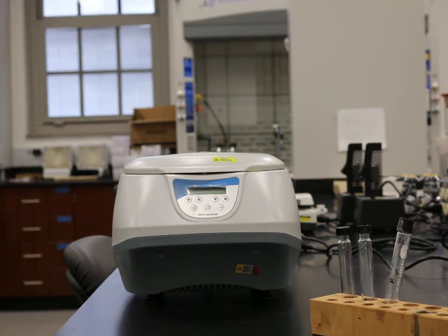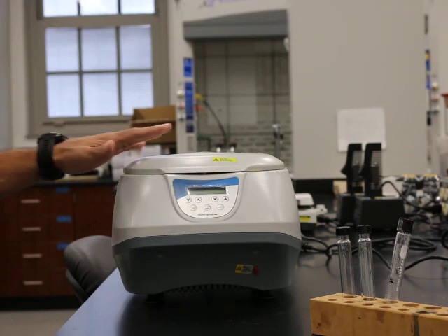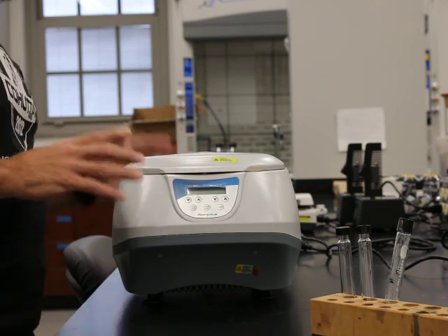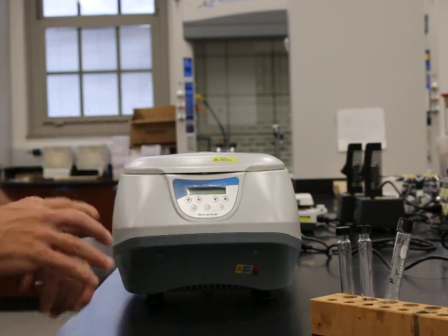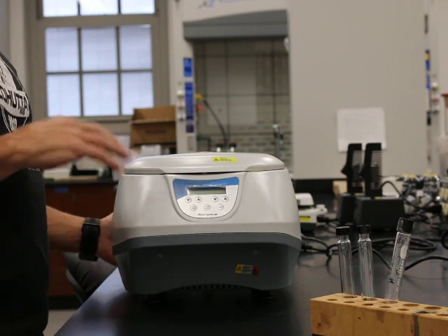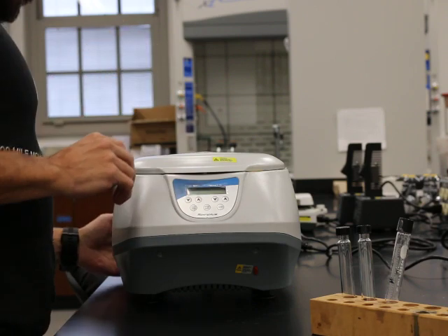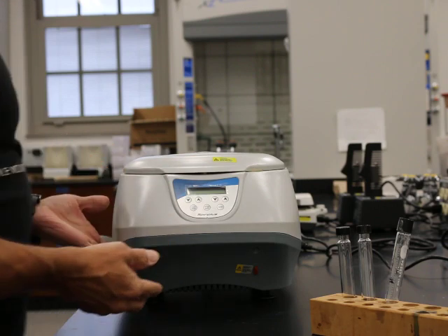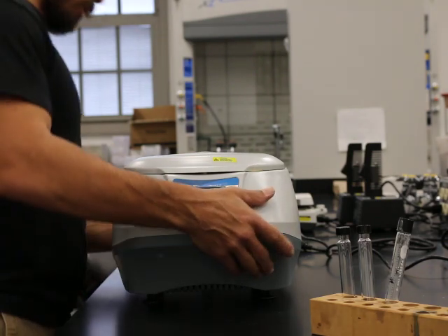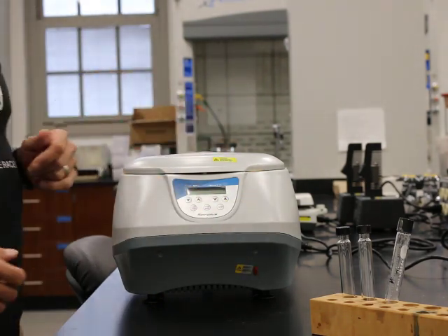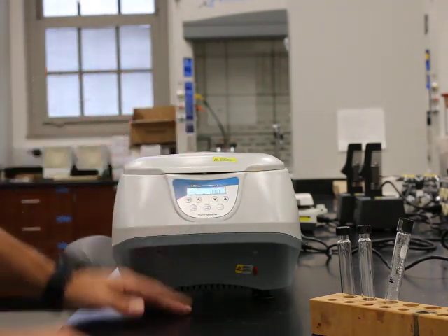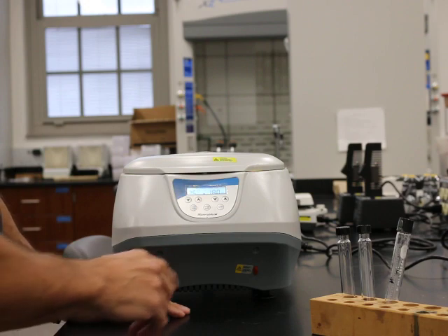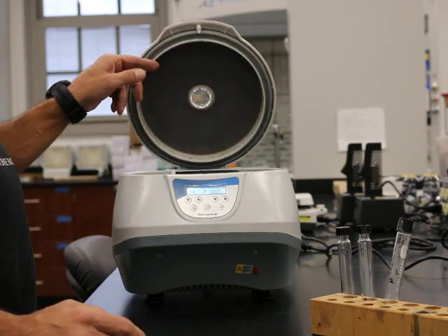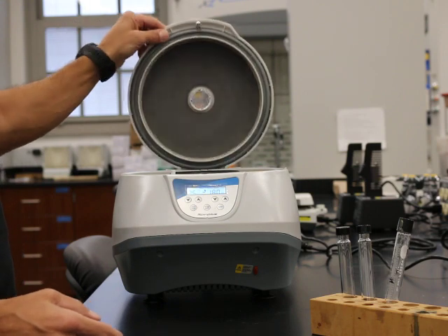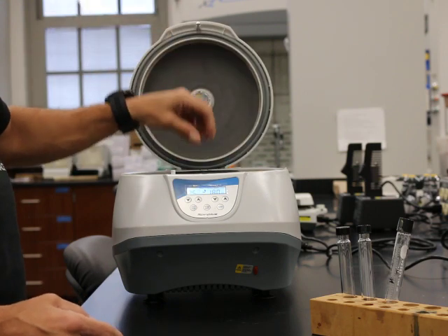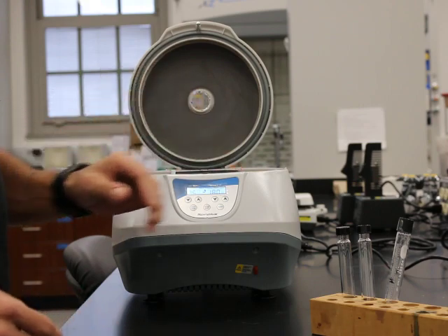All right, so this is going to be a brief video on how to use the high-speed centrifuge. And more or less it's pretty simple, but there's a couple things you have to pay attention to, otherwise you could damage the device. So when you walk up, chances are good it's not going to be on. There's a switch in the back. You'll have to push it. It will come on. The LED screen will come on, and you'll have to hit the open button, and it will open, and you can push it back so that you can access or see the inside spinner.